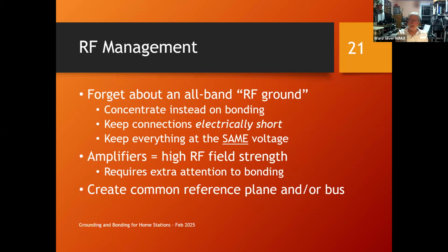One thing you can do - and we've all seen the picture of the copper pipe in the back, I'll get to that - is create a common reference plane. Remember that piece of aluminum flashing in my tower base single point ground panel? You can use that same flashing, lay it out on a wooden desk or table, and use it as a bonding surface, connecting things to it.